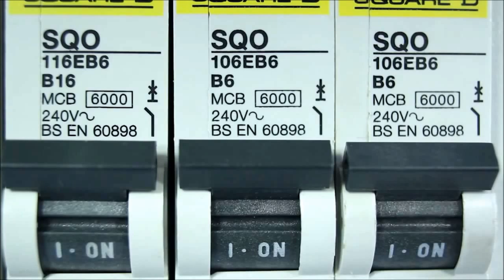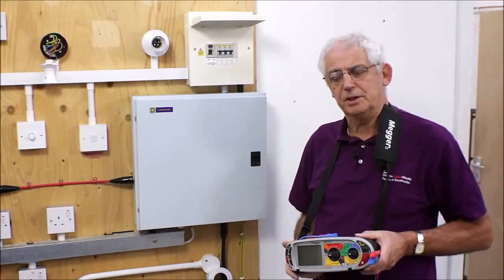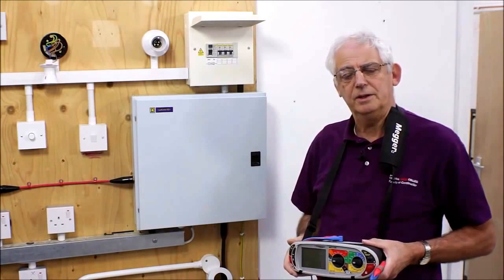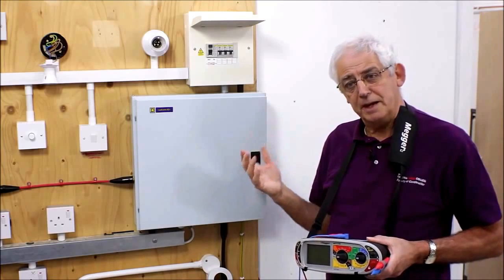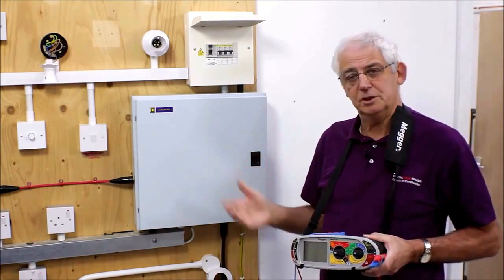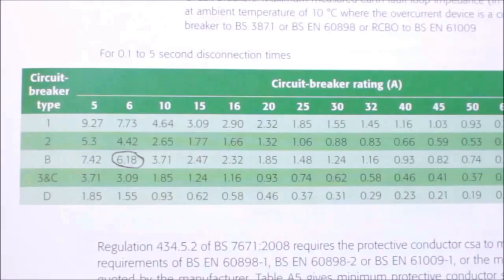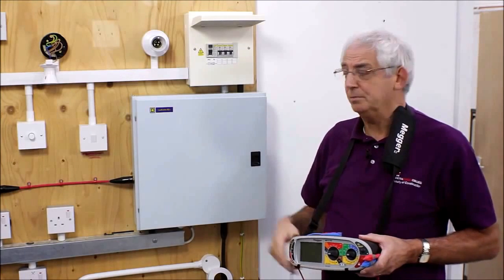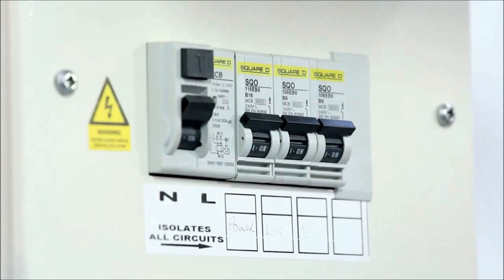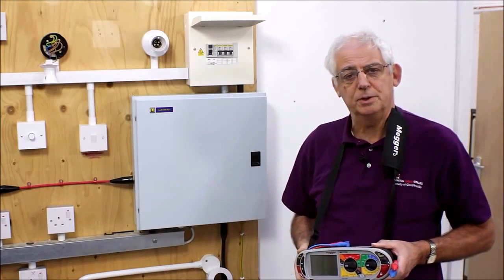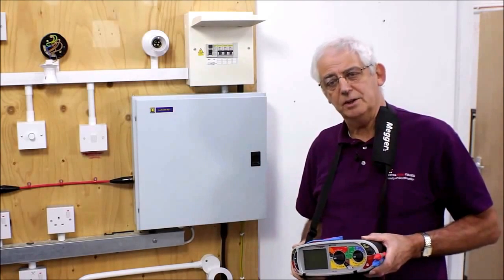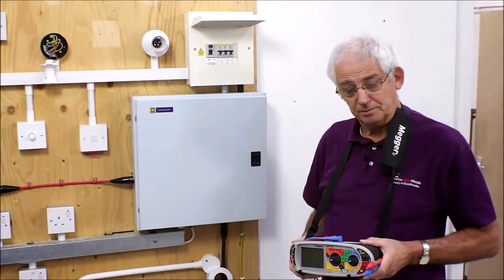What I need to do now is look on the chart, which I've got in Guidance Note 3 or the On-Site Guide, and that will give me the maximum value of Zs that the circuit would be permitted to have. The value for this particular device is 6.18 ohms. So now all I need to do, make sure everything's switched on, is go to the light point and take a value between the switched return and the earth with the switch turned on.